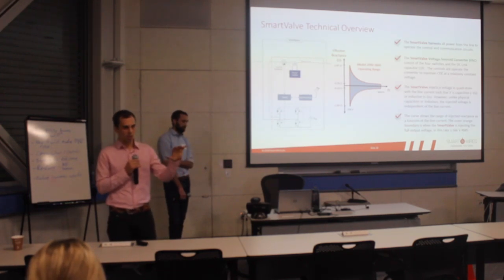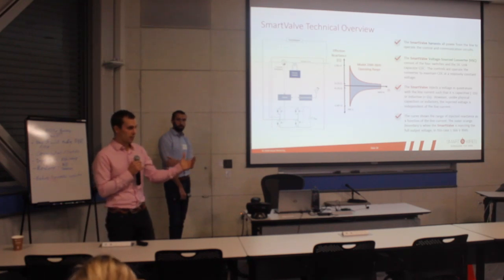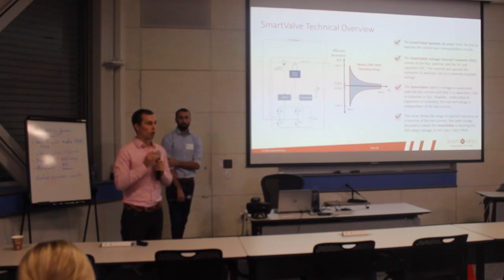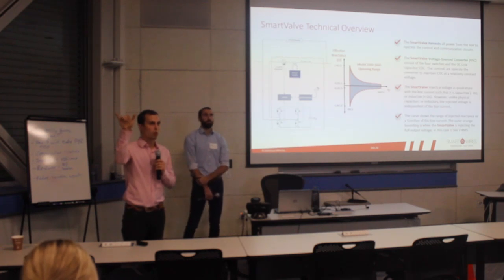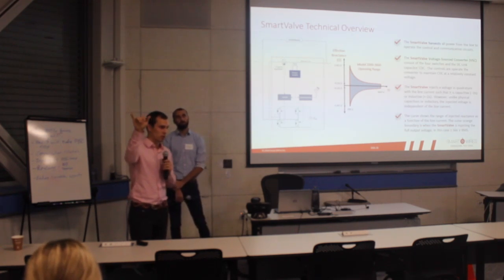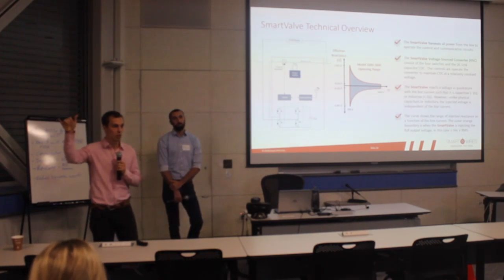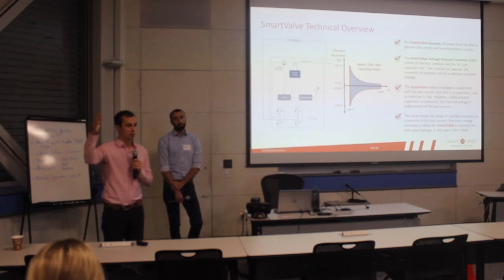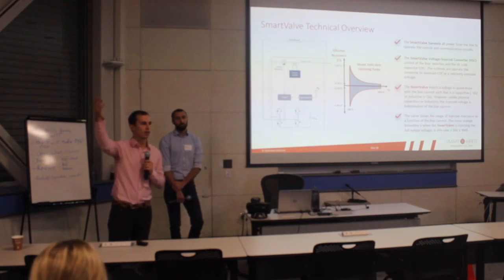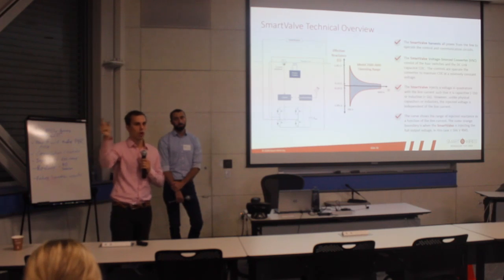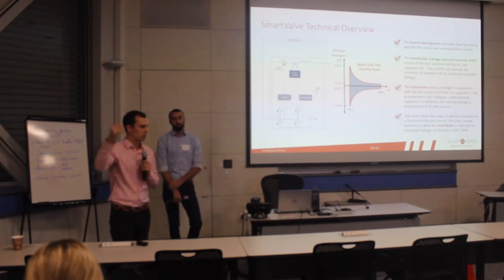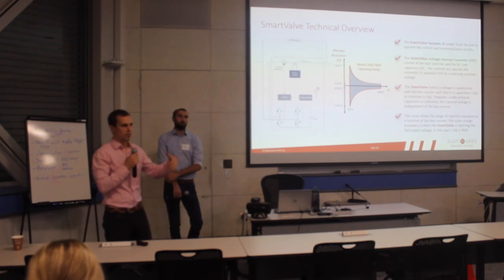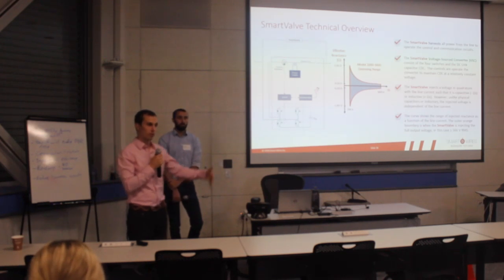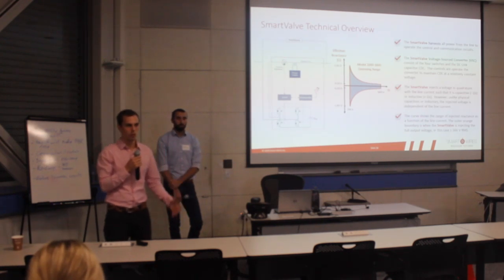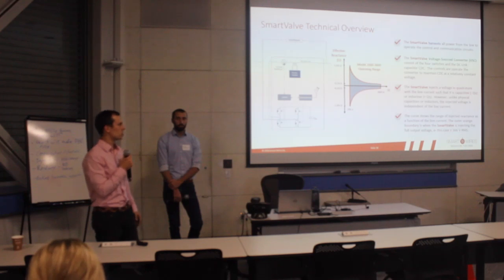If you think about voltage, we're on high voltage AC transmission lines. But because our product is in series with it, we don't really see a lot of voltage on our product. So that's one of the advantages we get: our product is essentially floating at line voltage, and whatever voltage drop is across our product is all the voltage we'll see. That voltage drop is how we inject, because we're injecting voltage on the line.